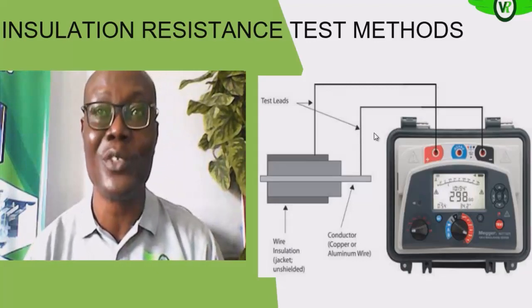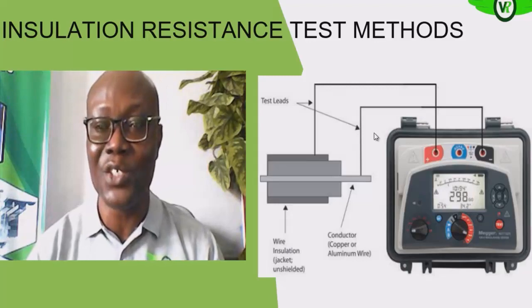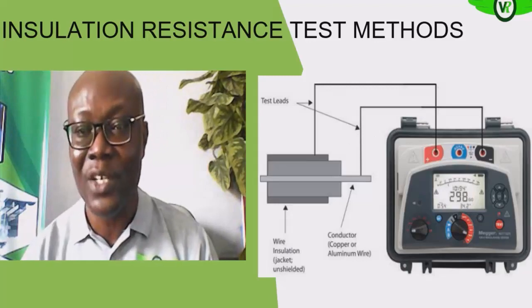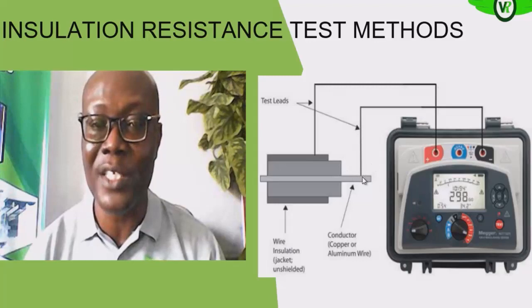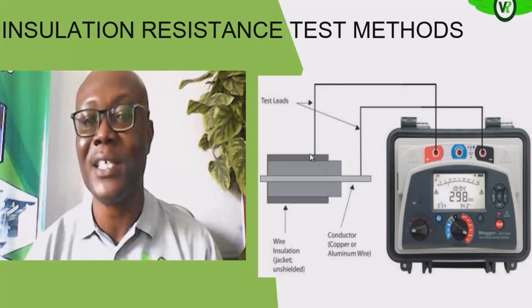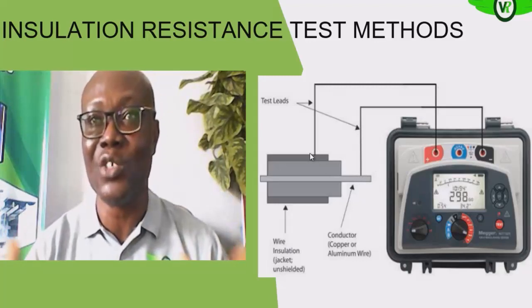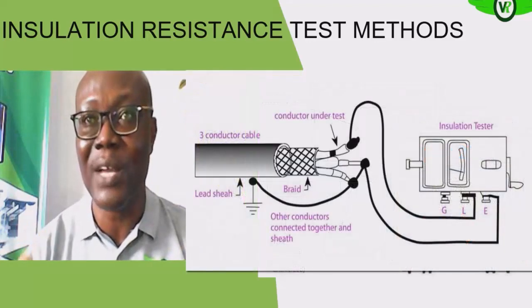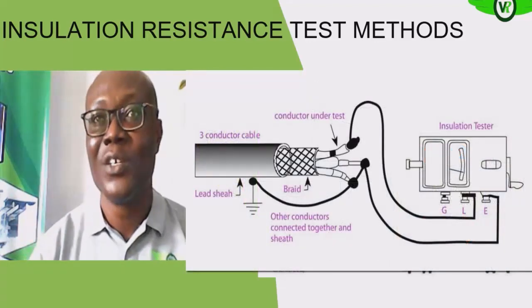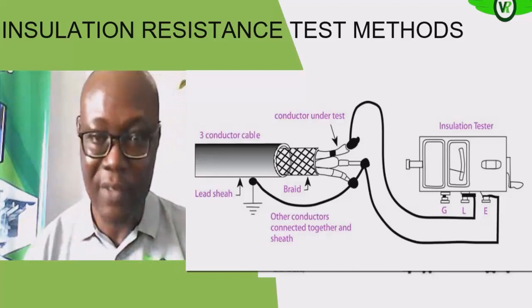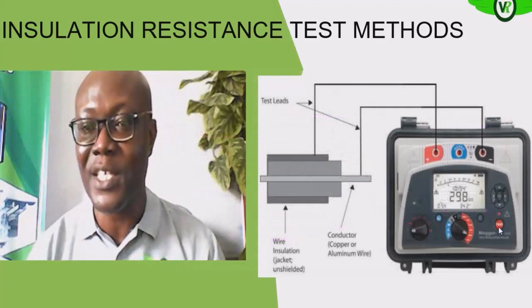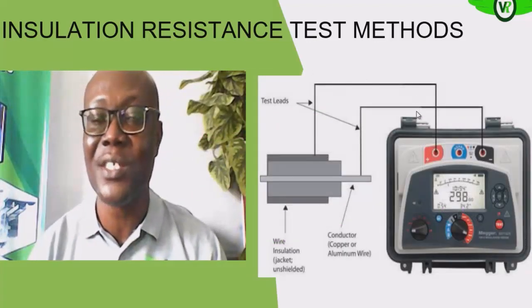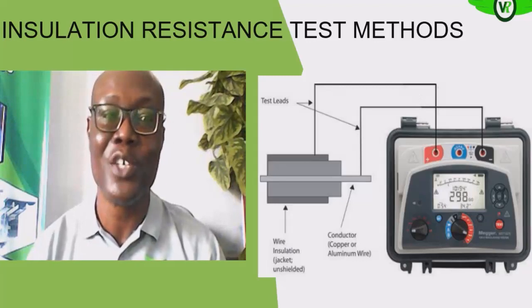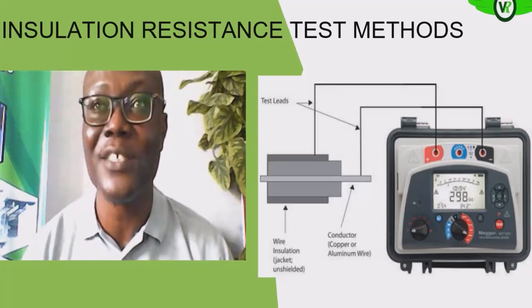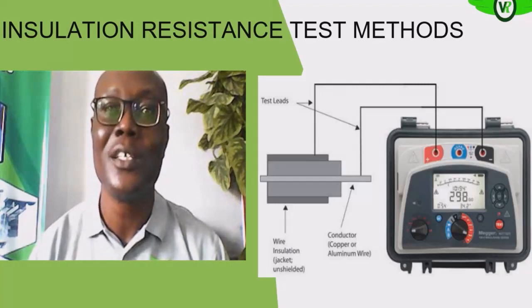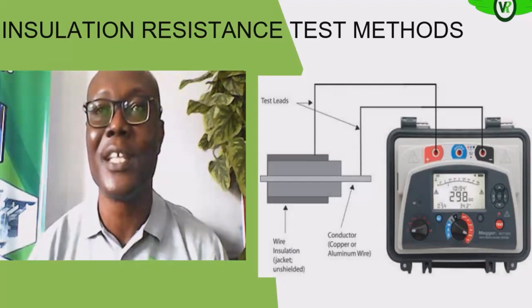Remember, we said for you to take this spot reading, after injection you allow 60 seconds to pass. So like we have here, once you connect here to line 1 and here to line 2, assuming you want to test the insulation between both phases, between line 1 and line 2, or between phase A and phase B, after making the connection, press this test button, and then you allow 60 seconds to elapse before you record your reading. So that is the first type of resistance test method.